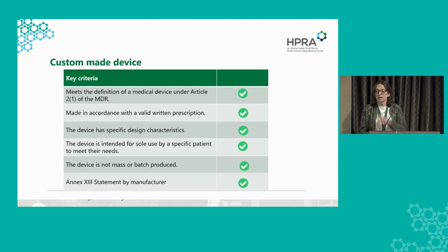So custom-made devices are specifically called out in the regulations throughout the chapters. There's a clear legal definition as to what qualifies as custom-made, and it means any medical device, first and foremost, specifically made in accordance with the written prescription of a qualified person, so a clinician, a physiotherapist, an occupational therapist, etc., by virtue of their professional qualification, which gives specific design characteristics to those devices, and it's intended solely for use on a specific patient. The device shouldn't be mass-produced or batch-produced, and the requirements are spelt out in Annex 13 of the Medical Device Regulation, and an Annex 13 statement needs to be prepared instead of the CE mark.